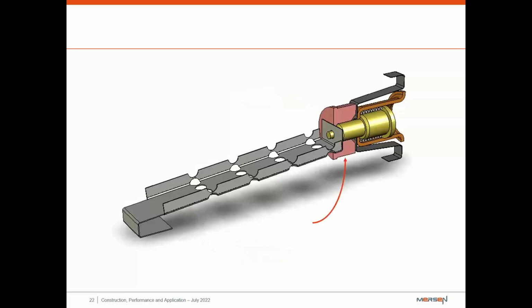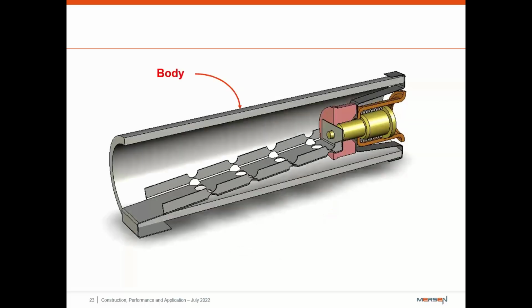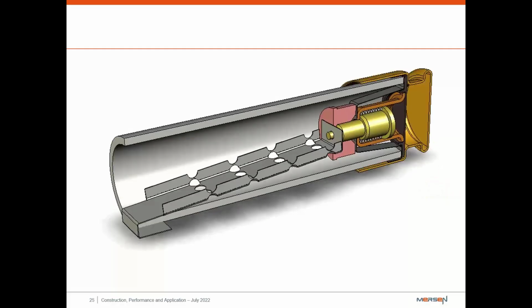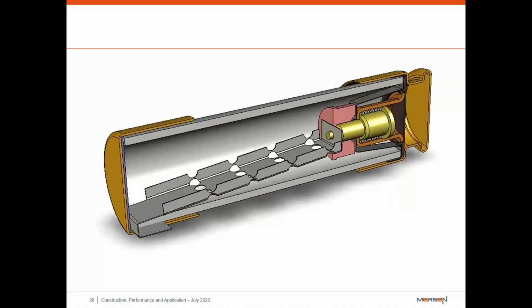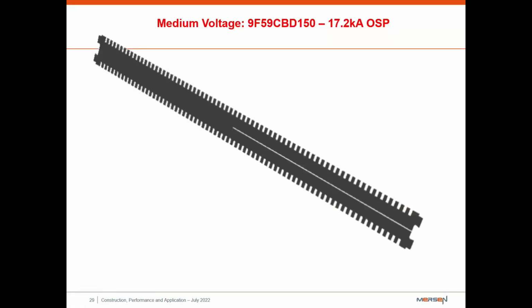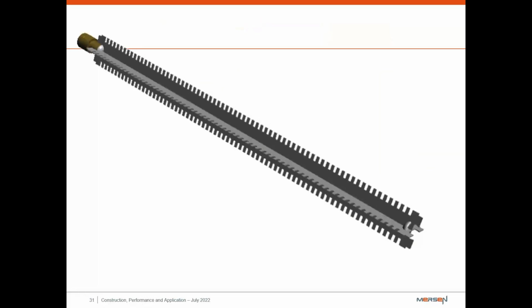We have a grommet to make sure that everything stays in place. And then we have our body that goes on the outside, a fiberglass washer on our end, a rejection style ferrule, and then the filler that goes inside, which is going to be that purified sand, a fiberglass washer for the other end, and then our non-rejection style ferrule. So getting into medium voltage fuses, this is what the interior looks like. We're going to have our stabilizers that keep everything in place, the ends that will actually connect into the application itself, and then our elements.